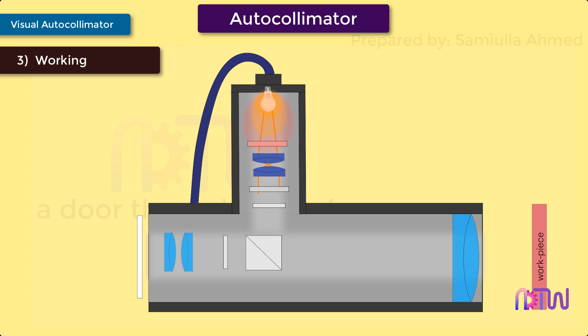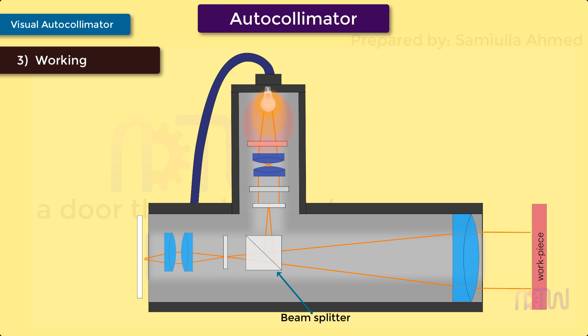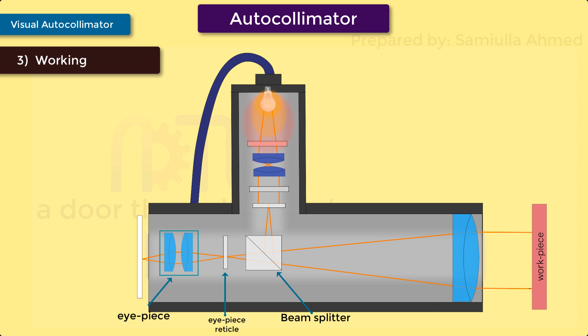After passing through the diffuser, the beam of light passes through the objective reticle and then falls onto the beam splitter. Here the beam of light splits into two and gets projected on both sides. The beam traveling on the left-hand side passes through the eyepiece reticle and eyepiece lens. On the other hand, the beam traveling on the right side passes through the objective lens and falls on the plane reflector.